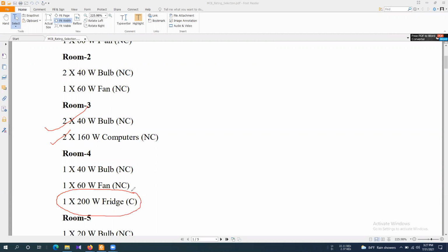While calculating this load to determine the perfect rating of the MCB and MCCB, this continuous and non-continuous factor has some parameters. In case of non-continuous load, you do not need any additional calculations. But whenever you consider a continuous load, you have to adjust some parameters, as it is always connected to the power system to allow protections.